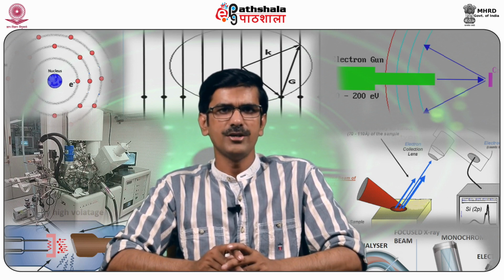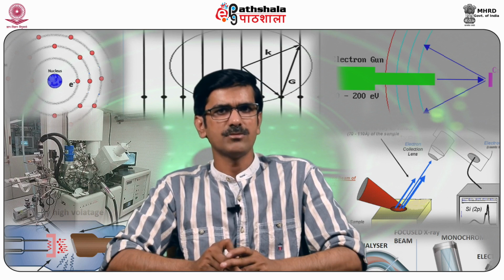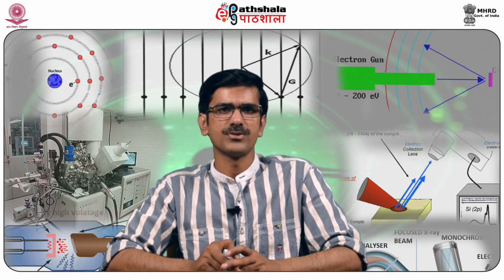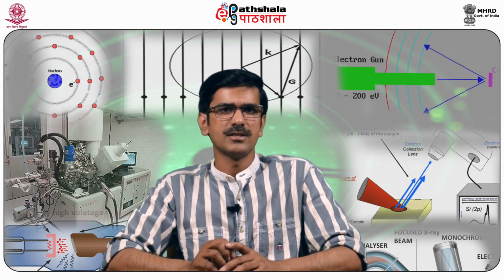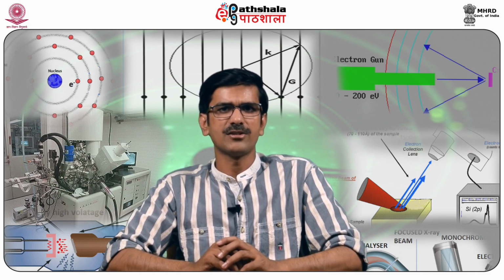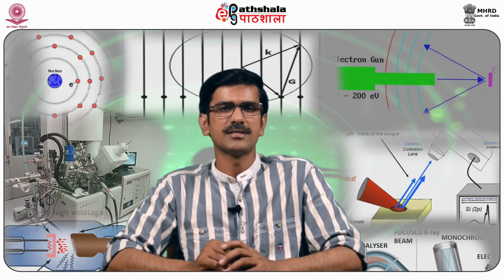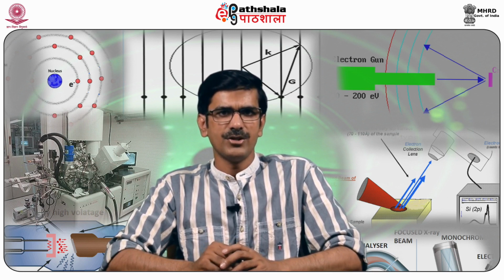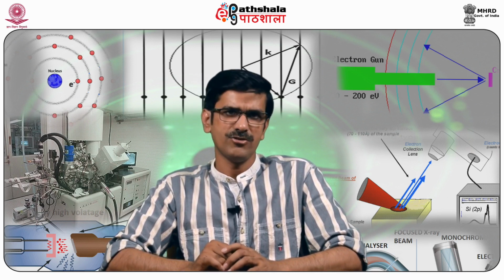In order to actually get well resolved, useful data, other components must be introduced into the instrument. To improve the resolution and intensity of the system, optics is added to the PES instrument. Electron optics are able to decelerate the photoelectrons through retardation of the electric field, and this energy is known as pass energy. The deceleration helps in raising the resolution but lowers the sensitivity also.